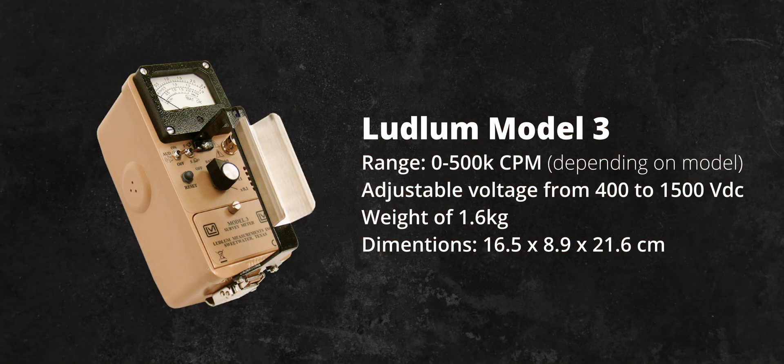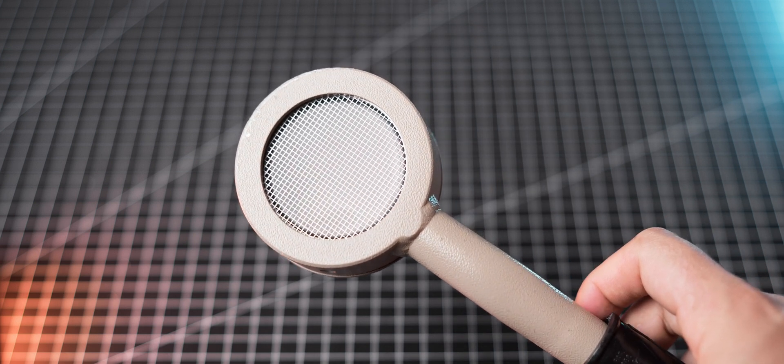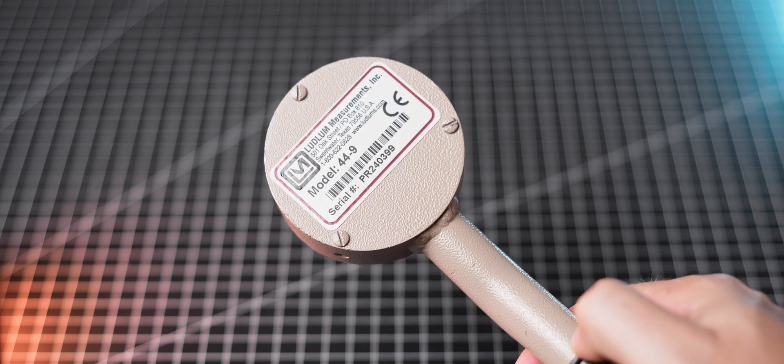The Ludlum Model 3 has a range from 0 to 500,000 CPM and can supply voltage to the probe between 400 and 1,500 volts. This flexibility allows it to work with a variety of different detectors, including scintillators and some neutron detectors. Most of the time I pair my Ludlum Model 3 with a 44-9 probe, though I do change that occasionally depending on the situation.